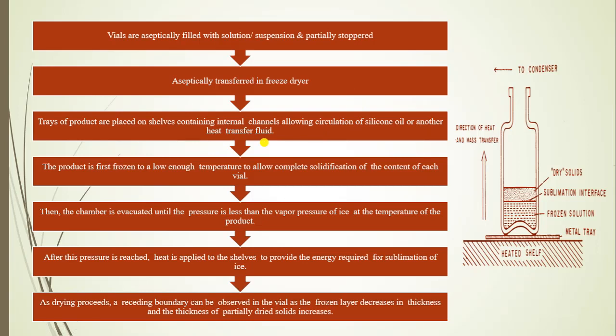Trays of the product are placed on shelves containing internal channels which allow circulation of silicon oil or other heat transfer fluid, which provides heat for freezing as well as for drying. The product is first frozen to a low enough temperature to allow complete solidification of the contents in each vial. After that, the chamber is evacuated until the pressure is less than the vapor pressure of ice at the temperature of the product. The pressure difference is an important parameter — if the pressure is not less than the vapor pressure of ice, sublimation does not take place.